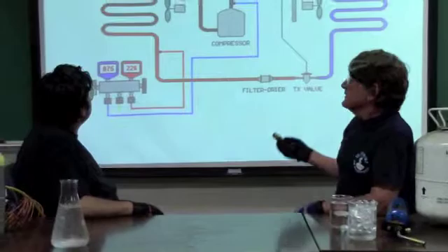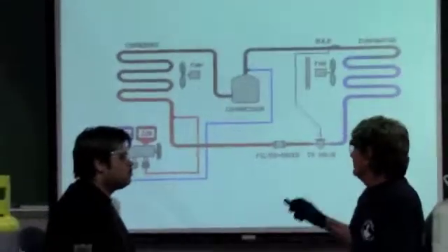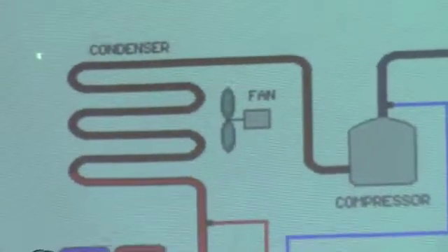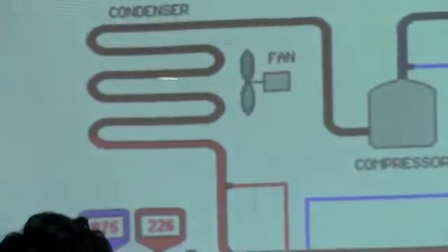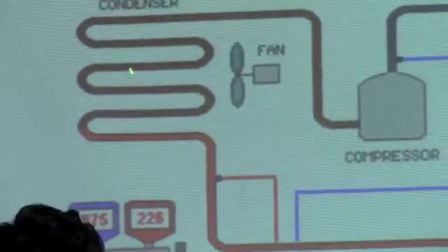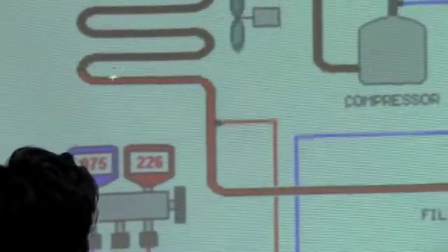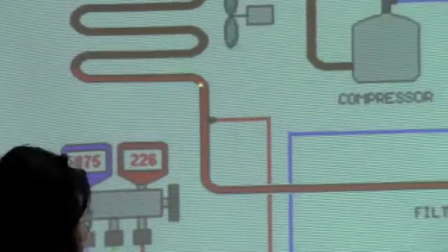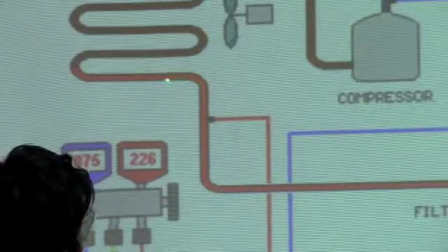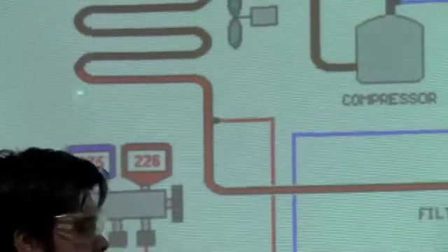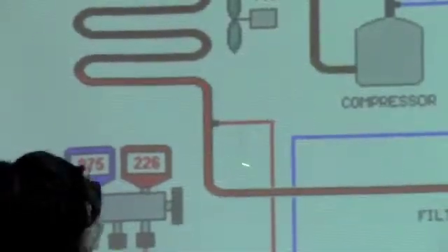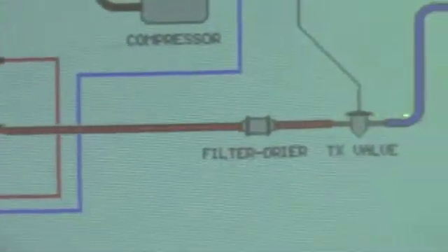Since we're talking about superheat and subcooling — if I leave the compressor, it comes off the compressor as superheated gas. It comes through here, gets saturated — now I have both gas and liquid. I pass the saturation curve, it all turns into subcooled. So I've saturated, removed some more heat from it, and got it subcooled, normally about 10 to 20 degrees or so.